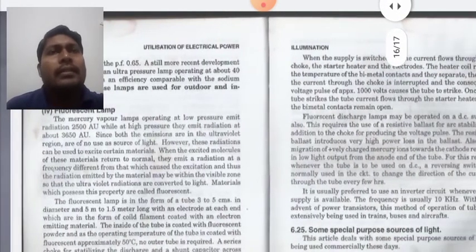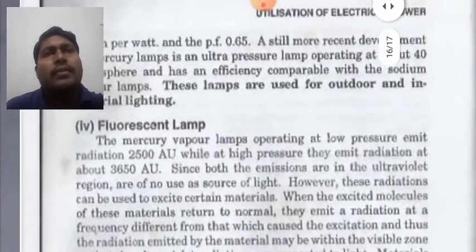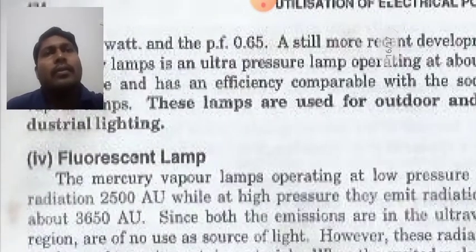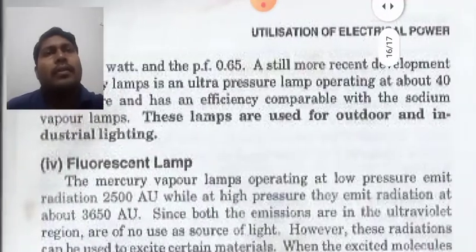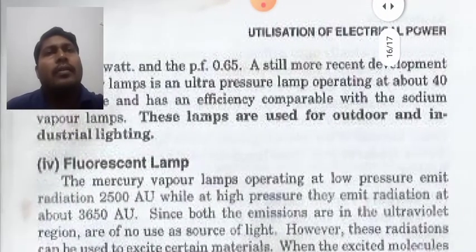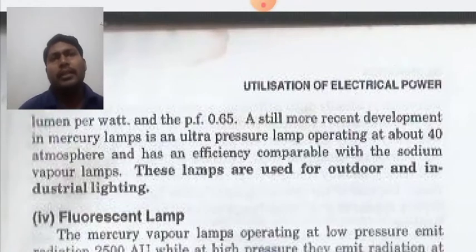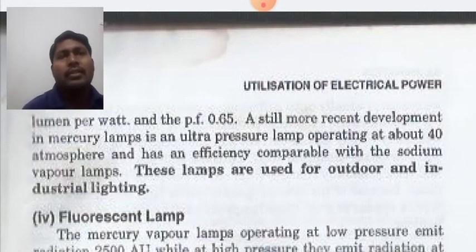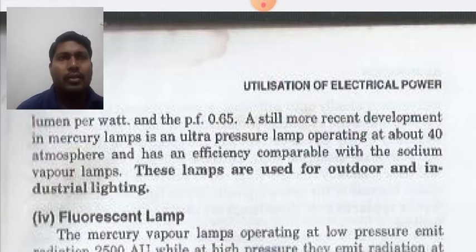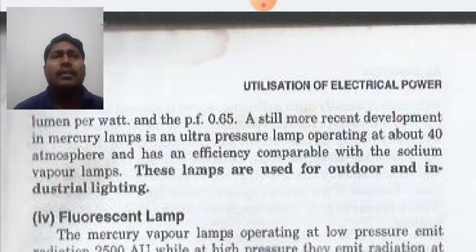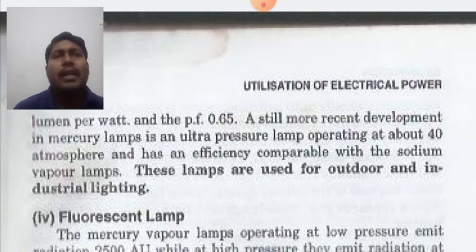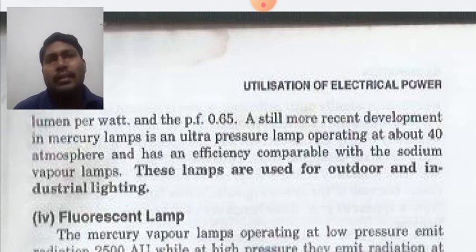The power factor of this lamp is 0.65. A still more recent development in mercury lamps is an ultra-pressure lamp operating at about 40 atmospheres, which has an efficiency comparable with sodium vapor lamps. These lamps are used for outdoor and industrial lighting.